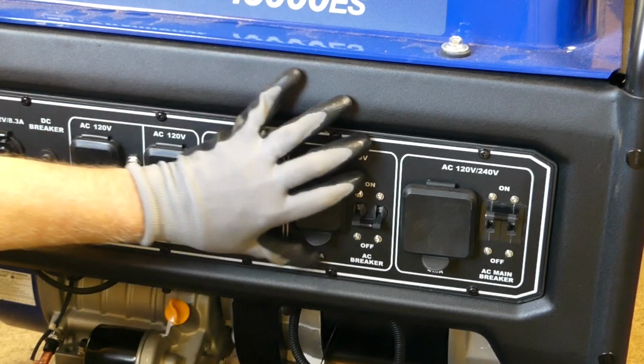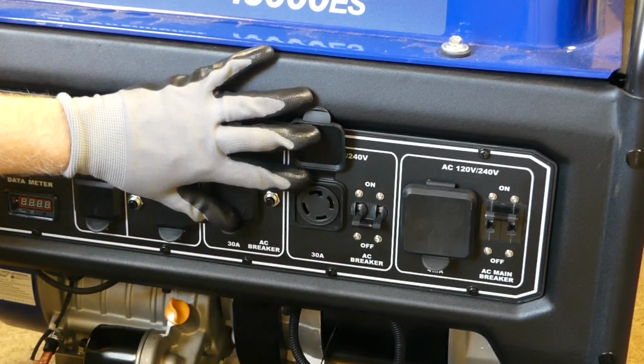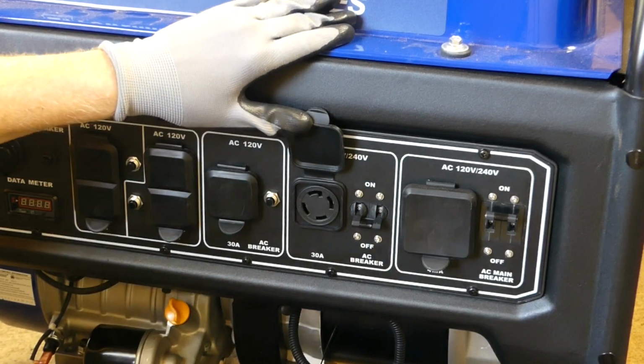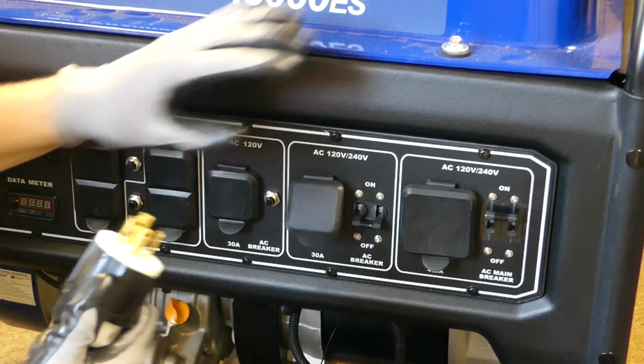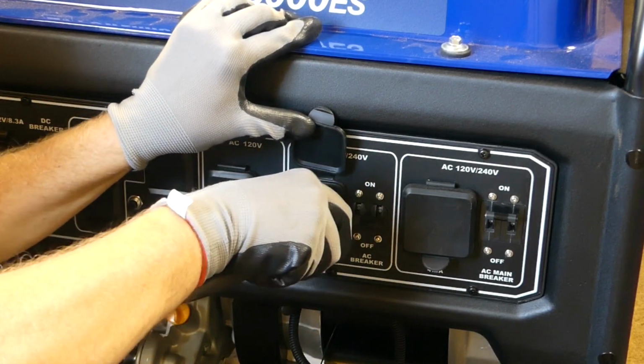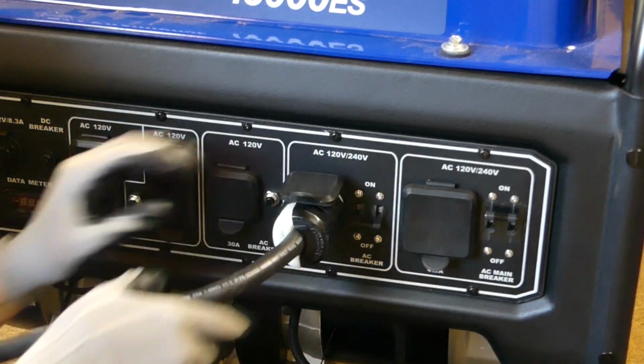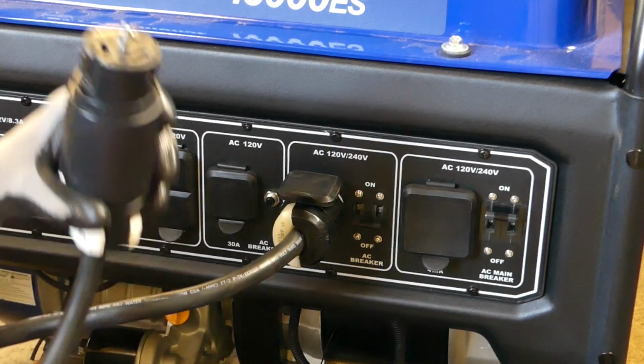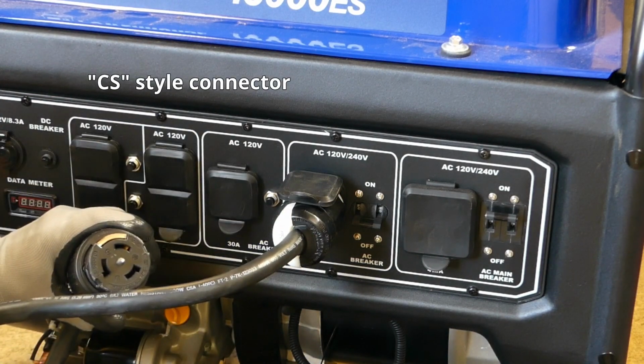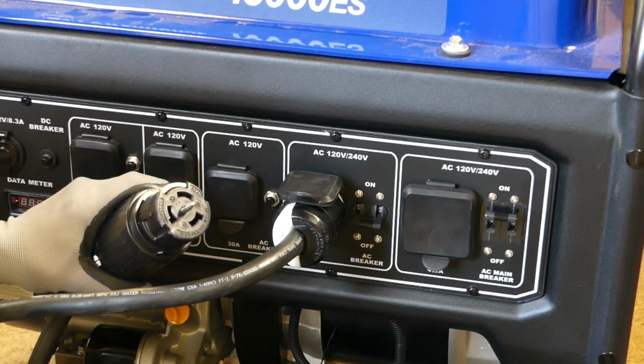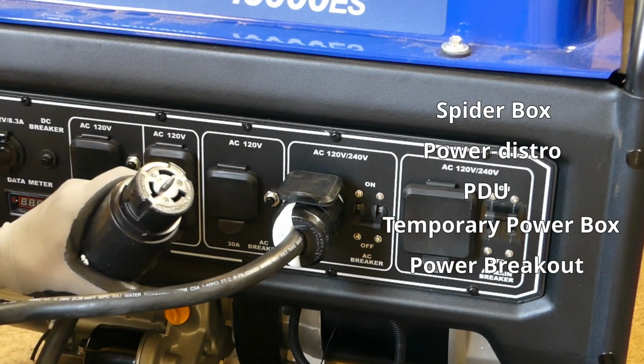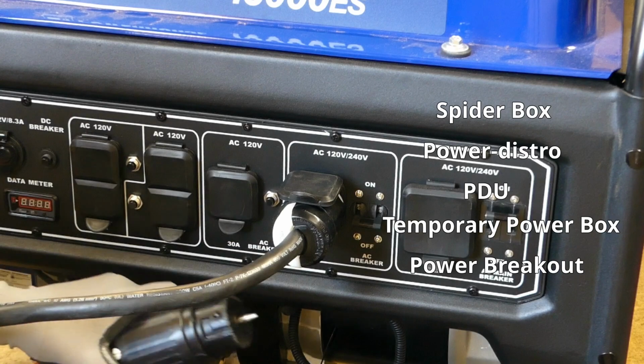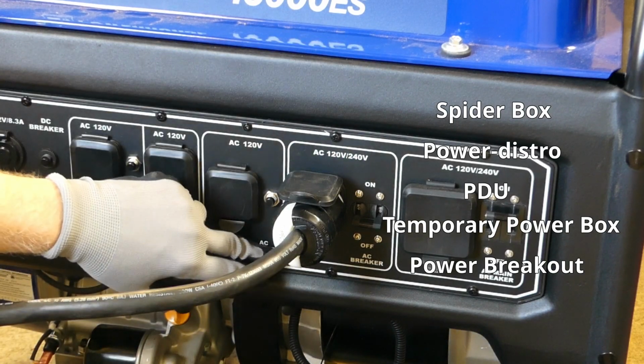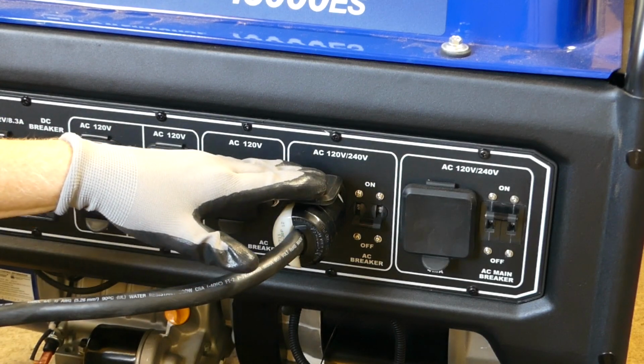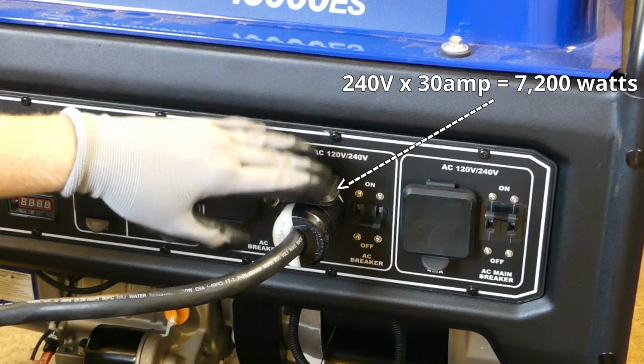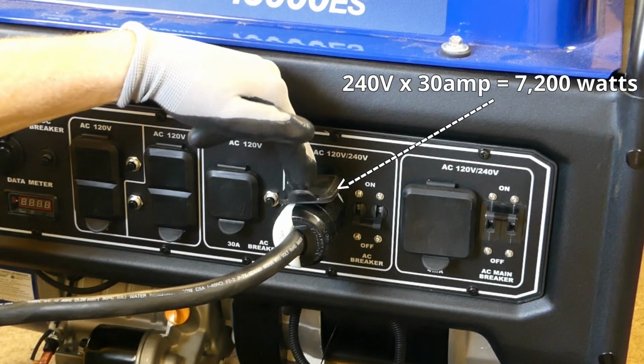The more power you have, the more availability to different types of receptacles you're going to get. All right, so on the 120/240, this is a 4-blade type of connection, and this is what these types of connectors are for. Just like the 30 amp one, this is a locking connector. And on the other end of it, for this particular one, we have what's called a CS connector. And this is what we can put into what is called a spider box, or a portable PDU unit. So our 120/240 volt 30 amp service, if we do the math on this, we come up with 7,200 watts available on this receptacle.